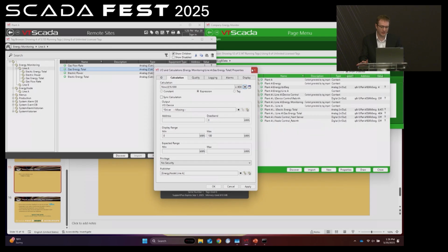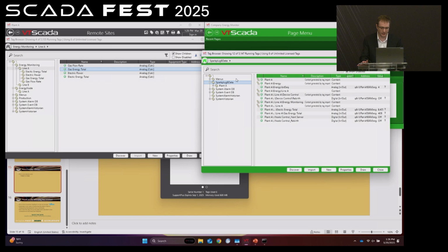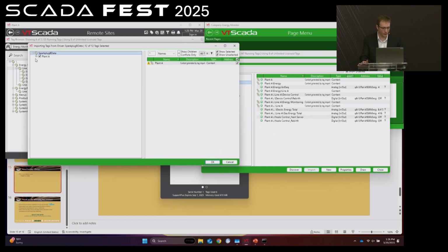There's another option you can do to get data in here. If you didn't want to use automatic publishing, there is another way. We do collect the data so you can actually use the import tool instead. So you can hit the import, and it'll show you all the things that we've received birth messages for, and you can pick and choose from this. So maybe you don't need all this other information about the next server rebirth controls. Maybe that's something you don't care about. You're probably better off using the import tool, picking the I/Os on your second app that your first app is publishing, and getting the subset of the tree that you want. And then when you do it this way, you can cut and paste these wherever you want in the tree. And as long as you're not adjusting the address field, it'll still get the data. They don't have to be in this part of the tree.